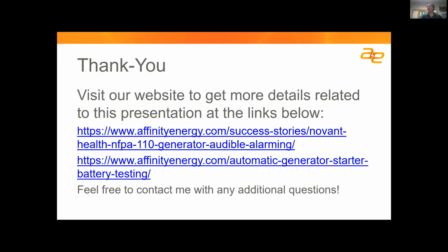I do know we had an interesting experience with one healthcare provider where the previous solution's siren and dB level was actually pretty quiet. I don't know if the standard calls out how loud it needs to be, but management asked us to provide a very loud siren as part of that panel. We found that drove the technicians crazy, because they weren't used to it. One challenge is that during monthly testing you typically have to take the generator out of auto and put it into manual, which creates an alarm telling you the emergency control system is in manual.